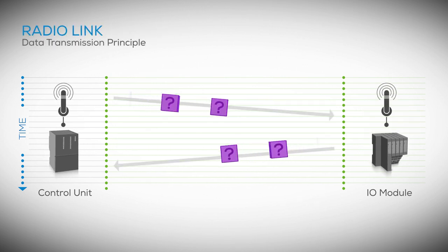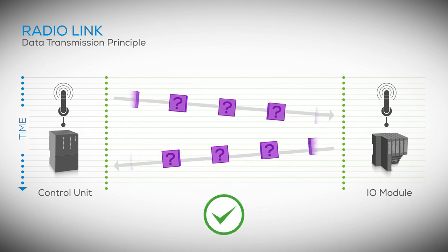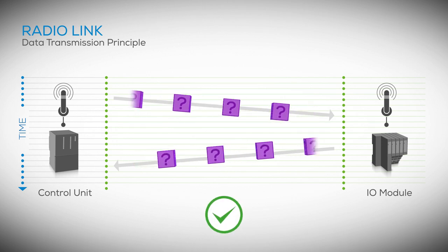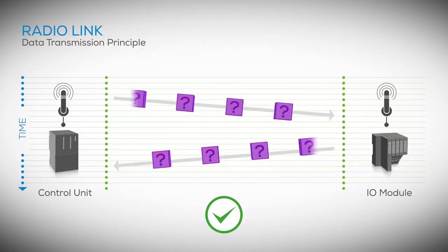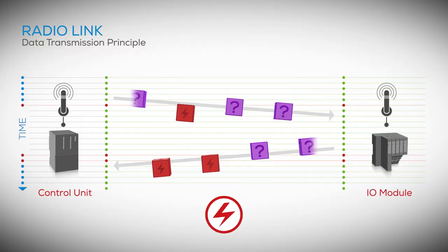With a radio connection, the data packets take longer to arrive, and if a short interruption occurs, the timeout will cause lost data packets. This simply means the controller or the I/O module does not receive several data packets and a bus error occurs. This usually leads to a plant shutdown.